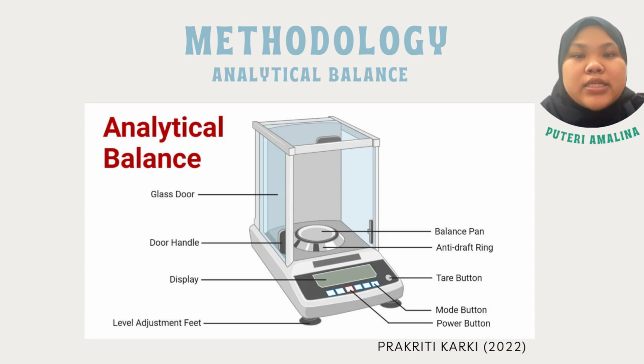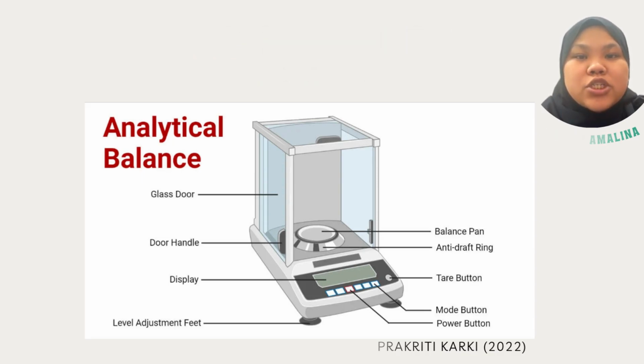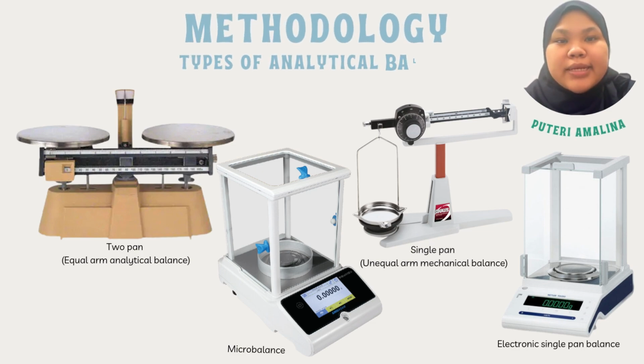On the balance, it has a display panel where it displays various information like results, errors, function settings, and functions in progress. An analytical balance must have a balance pan where it holds the sample material for the mass measurement, and it comes with an anti-draft ring. Lastly, we have a glass door to protect the samples from outside factors that can compromise the precision. There are various types of analytical balance. There are two-pan equal arm analytical balance, single-pan unequal arm analytical balance, microbalance, and electronic single-pan balance.